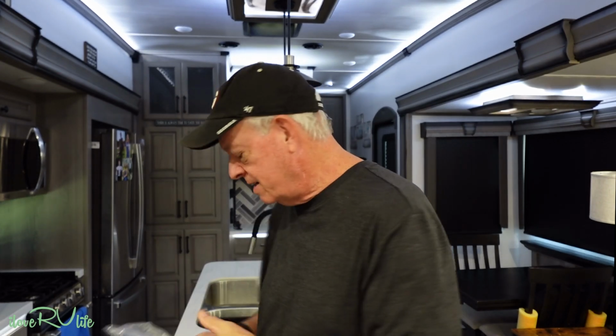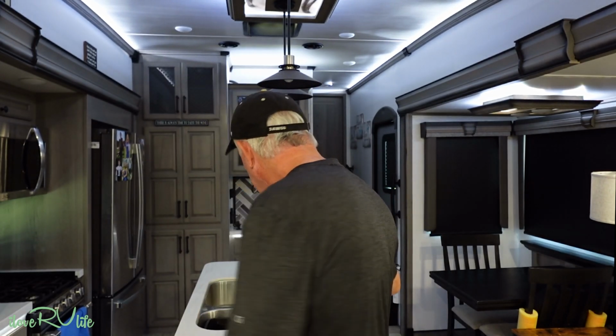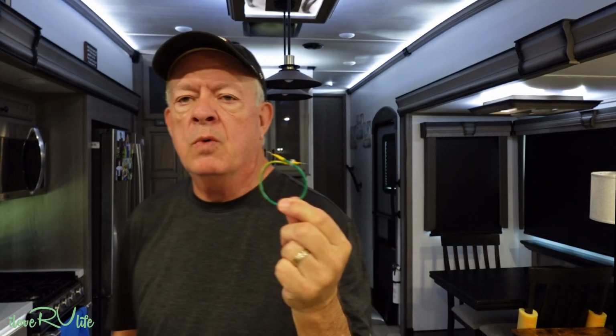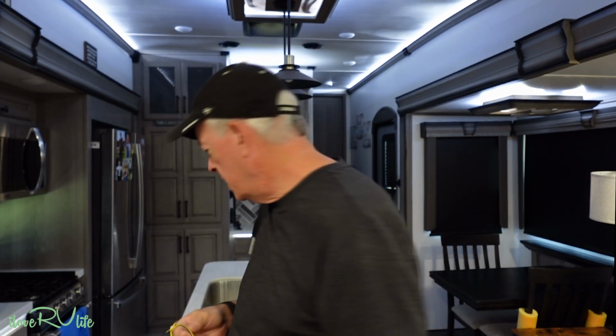And the last thing they provide is a jumper wire. A lot of devices can't have what's called an open neutral, so you may have to strap the ground to neutral to keep certain devices from alerting or failing when they detect an open neutral. Just in case you need that, they've included it. So it's a very, very nice unit.